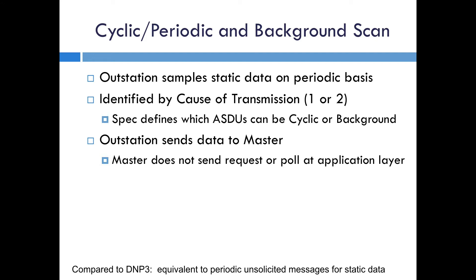Cyclic and background scan are very similar, but cyclic is typically used with a faster sampling time. The specification doesn't really say why you would do cyclic versus background scan, but generally background scan just has a slower period. The important thing here is that the master is not sending a poll request at the application layer — the outstation is directly sending this data to the master on a periodic basis. In some ways this is equivalent to an unsolicited response in DNP3, however it's done on a periodic basis. In DNP3, unsolicited responses always contain event data or data changes, whereas cyclic and background scan is still static data being sent on a regular basis without the need for a poll from the master.